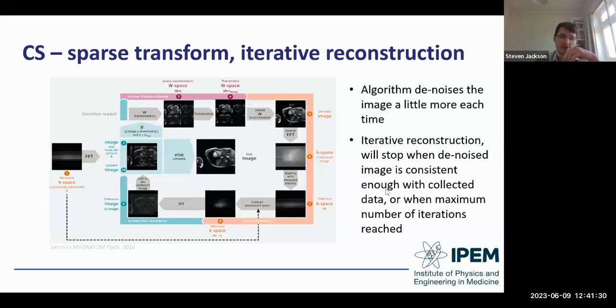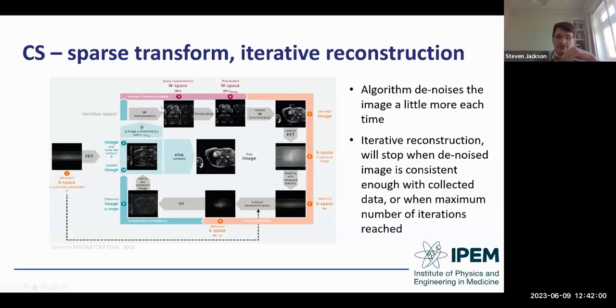For each denoising step, the result is compared to the original collected data. If it's consistent enough with the collected data, or the maximum number of iterations has been reached, the reconstruction stops and the final image is output. That's the broad brushstroke of how these algorithms work — each individual manufacturer does it slightly differently.